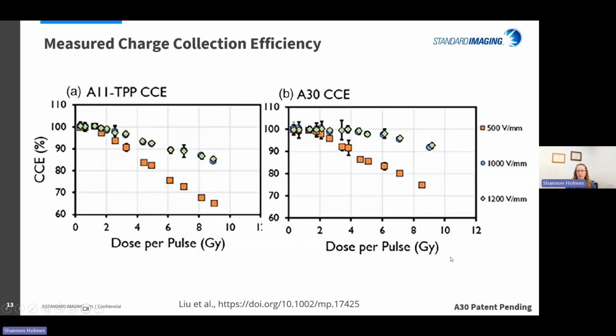Now in real life, with measurements with the A11 thin parallel plate version and the A30, you can see that we actually had some significant fall off with the broader chamber, the larger chamber, at a lower dose per pulse, where the A30 kept a little bit closer to that simplistic model. This is most likely due more to electrometer impulse response because of the volume of that chamber than necessarily the chamber behavior, but it is an interplay of the two.